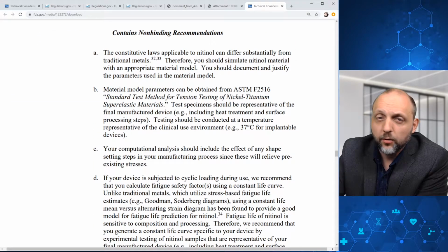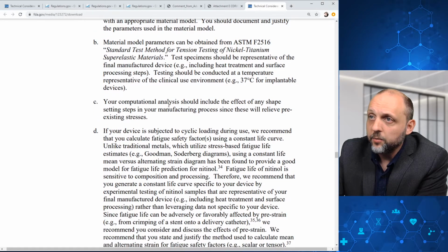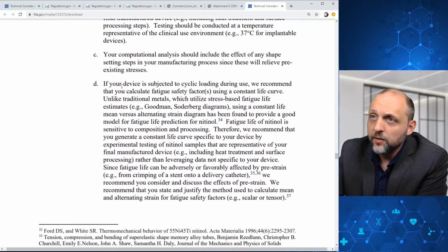Document and justify the parameters used in the material model. Testing should be conducted at a temperature representative of the clinical use environment. Your computational analysis should include the effect of any shape-setting steps in your manufacturing process.